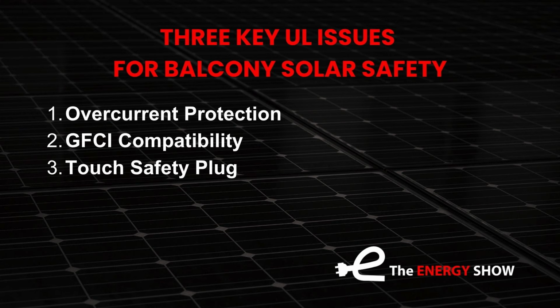First, overcurrent protection, also known as a short circuit. With balcony solar, there are now two potential sources of power on a single electrical circuit protected by a single electrical breaker, and that could theoretically, though it's almost impossible, create an overload. That overload is solvable now based on the findings in the UL standard when they're implemented, solvable with a dedicated circuit for balcony solar. So eventually, every balcony solar system is likely to have a dedicated receptacle with the necessary short circuit protections.